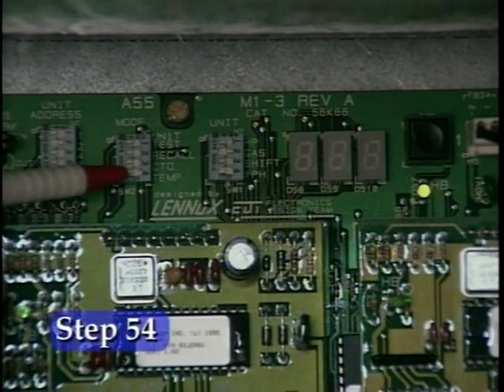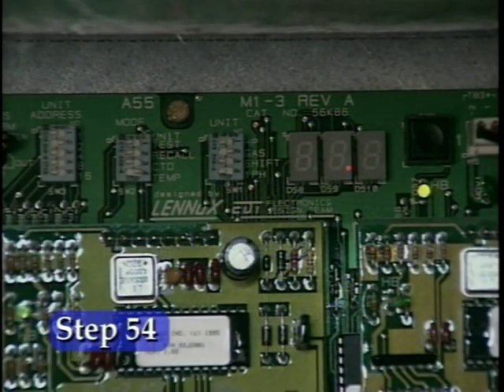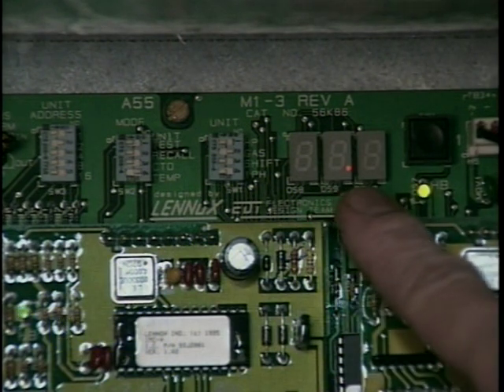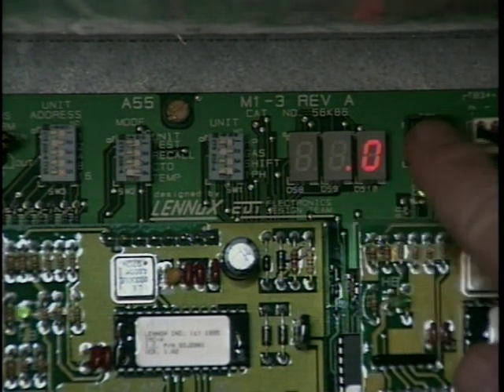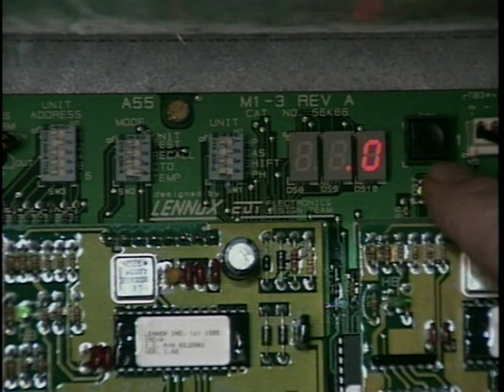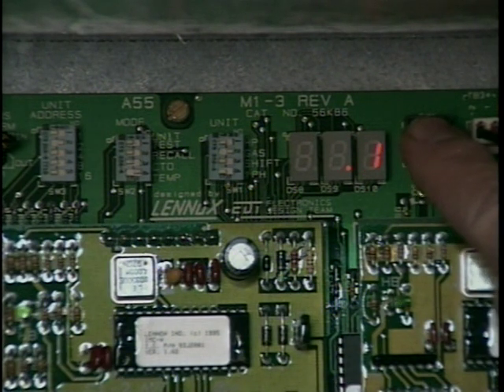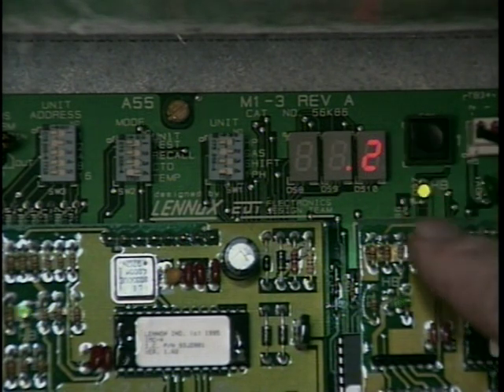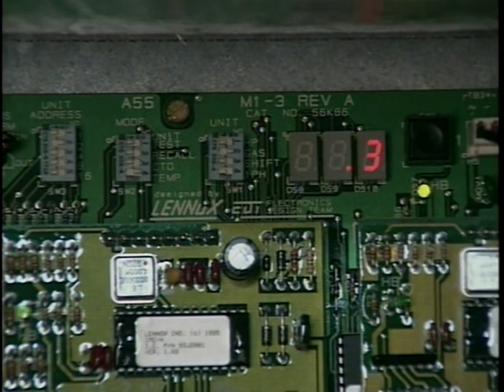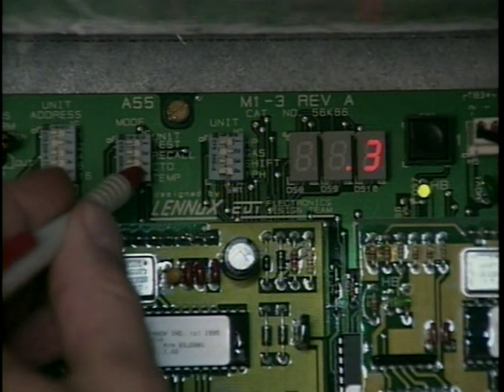Place switch 4 on SW2 on. The LED readout should alternate between point 0 and the ambient air temperature. Press the display push button twice to advance to point 2. The LED readout will alternate between point 2 and the supply air temperature. Record the heating supply temperature in space 54. After recording temperatures, place switch 4 on SW2 off.